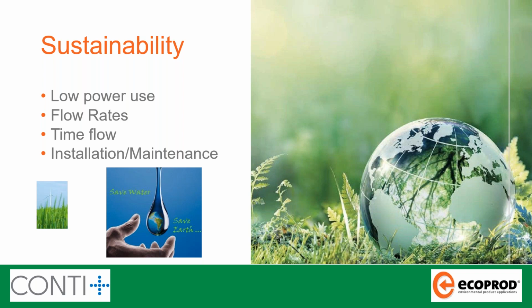Now, typically for a shower, rates of 12, 14 and 16 litres of water a minute are not unusual. However, we would try and mitigate that to give you flow rates around the 8 to 9 litres. Of course, these can be overridden if people want more water, but obviously water is a resource we all need to consider saving. The key for me is that balance between a good flow rate at a lesser flow rate to make sure that the shower is an experience that's enjoyable and it performs its duty.